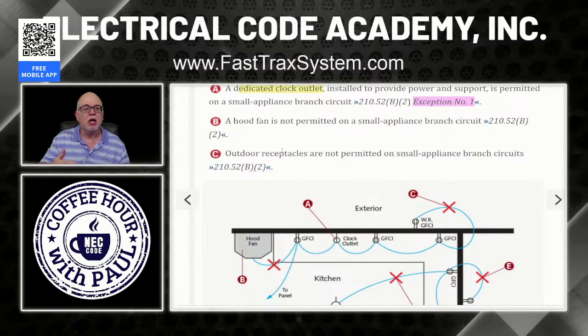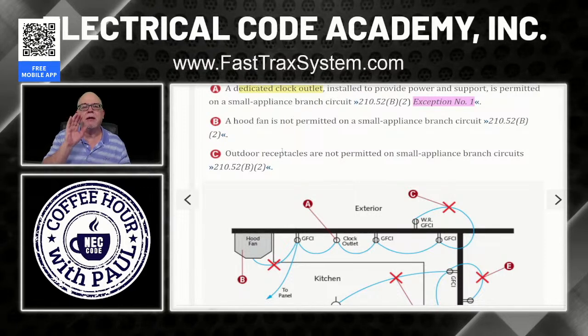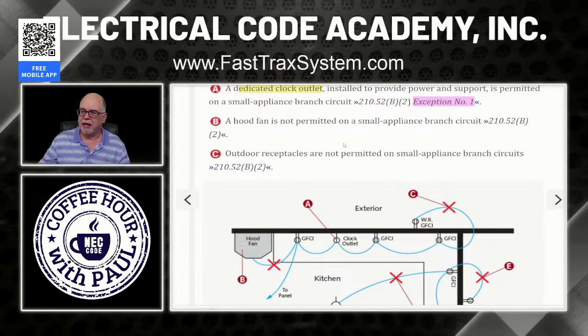But also, looking at the load that it draws, and it's typically cord and plug, then you have to be careful because we're going to have to limit things to like 80% of the rating. So just know that the microwave cannot be on the small appliance branch circuit.